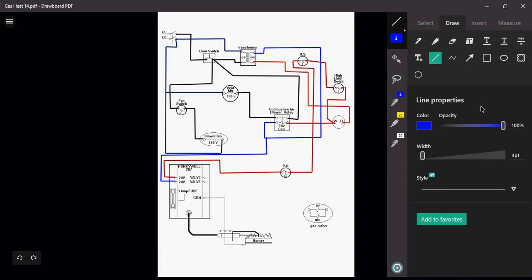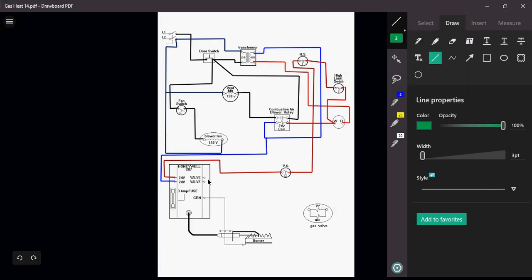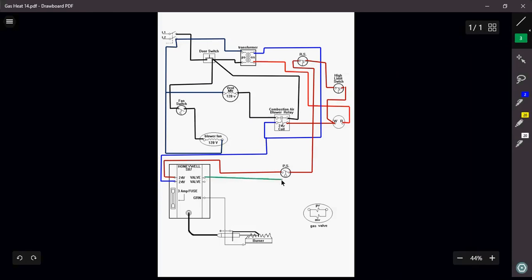And to wire the rest of this, it is honestly very, very simple. When you're looking at any ignition module, usually they are pretty self-explanatory. Everything is pretty much labeled for you. It tells you where your gas valve wires are supposed to be wired, where your ignition wires, your sensors, all that stuff are all going to be wired. So for this, I'm just going to use green. I'm just simply going to come out of my valves and go in one side, come back out the other. And I'm just going to wire in my gas valve, my 24 volts.